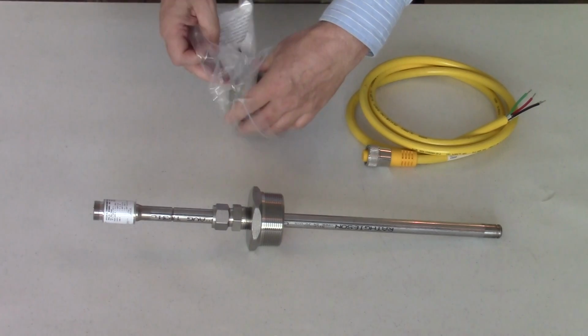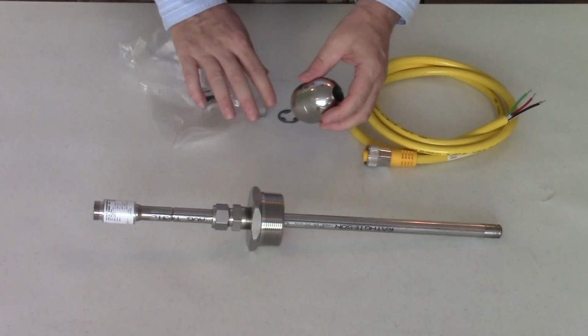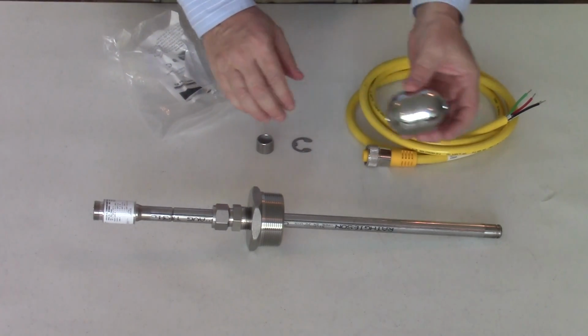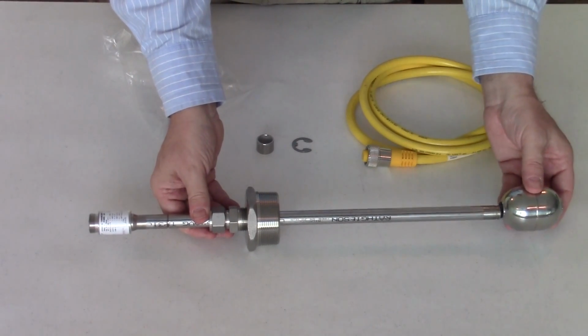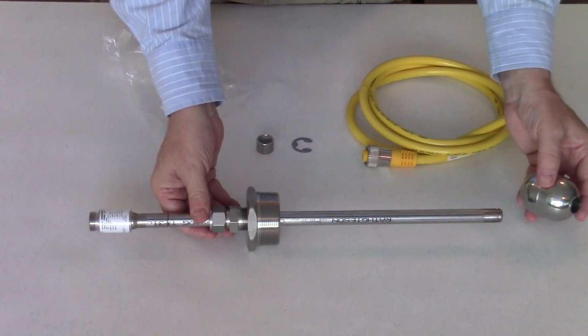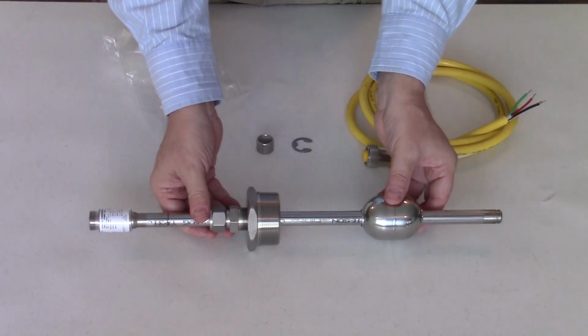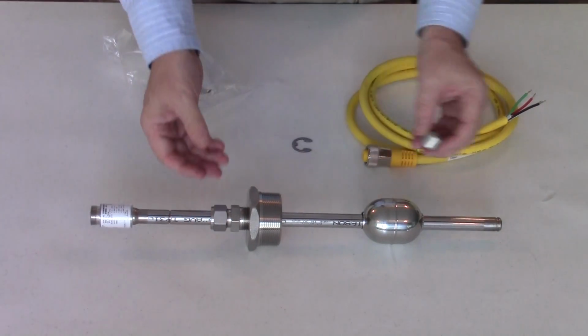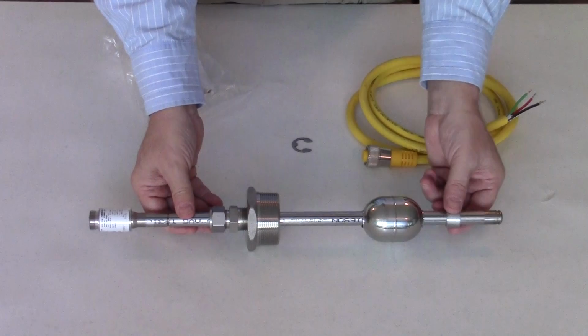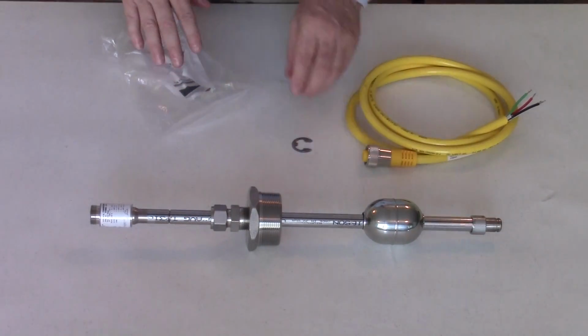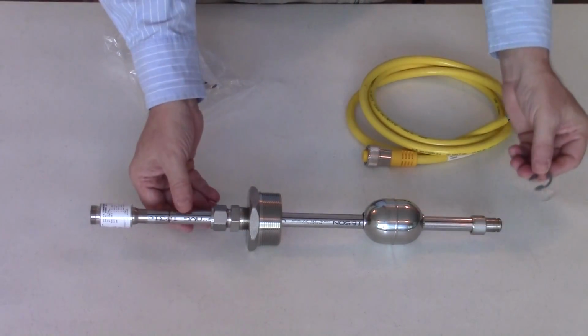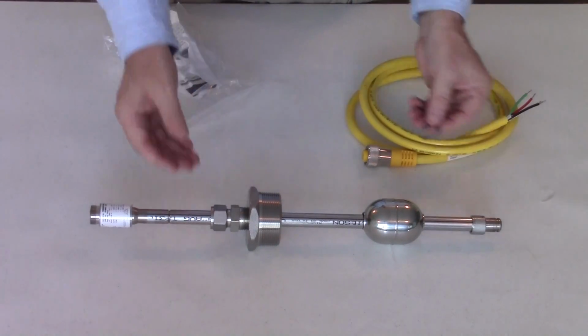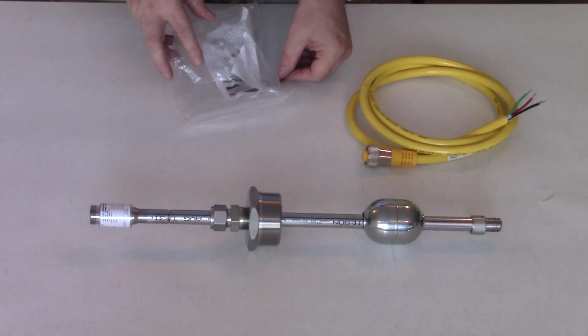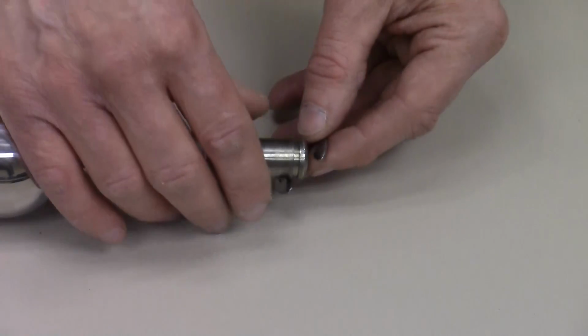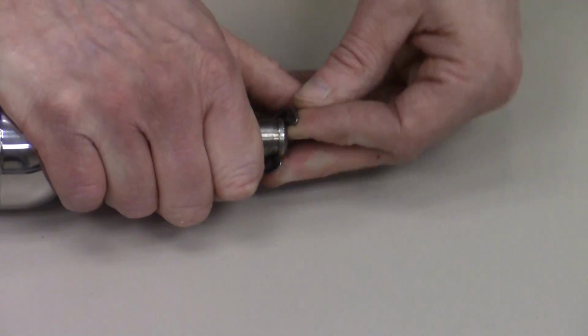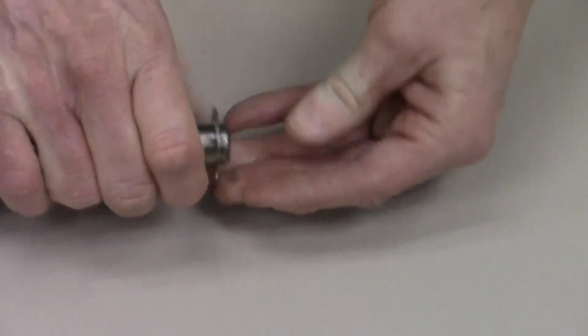A float kit has a float, a spacer, and a retaining clip. The float can be installed either way. There is no top or bottom on this particular float. The spacer goes at the bottom to prevent the float from going into the bottom deadband area. And lastly, the retaining clip is pressed into the groove near the end of the sensor's tube. A retaining clip is installed to keep all of the accessories within the tube.